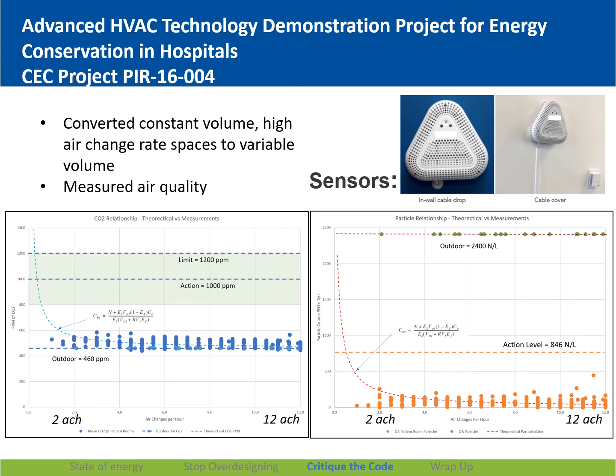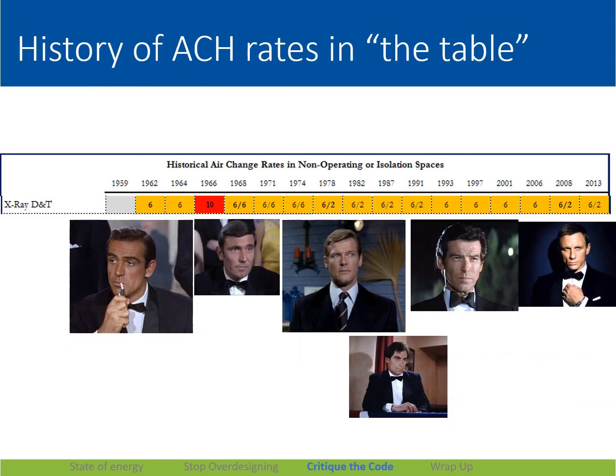The other really amazing thing about this project is that we're the first people to do it. You would think that after talking about air changes for 50 years, somebody would have checked whether those air changes do any good in controlling contaminants in the environment. And it turns out, whoops, they don't. So here's how I'll wrap up on Standard 170. This is the chart I've shown before. This is the standard air change rate in X-ray rooms plotted against the actor who played James Bond.